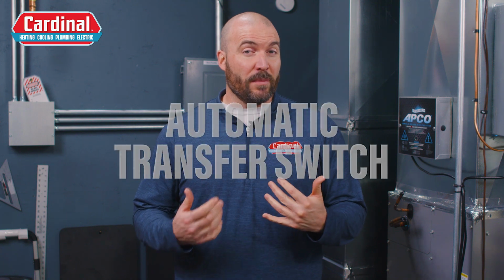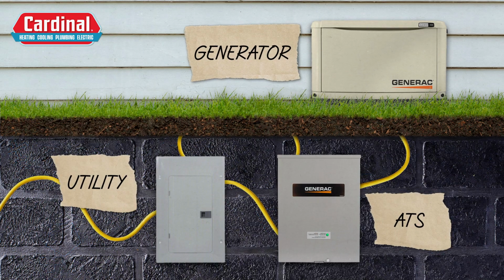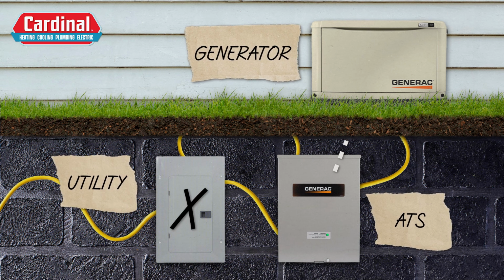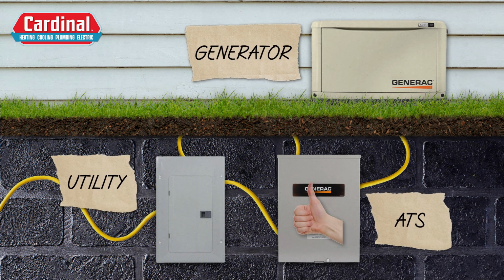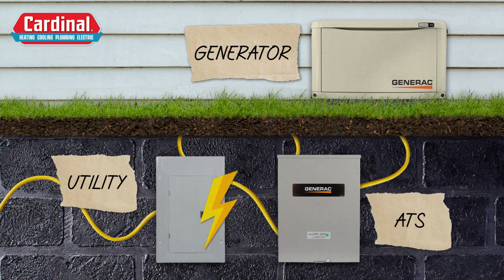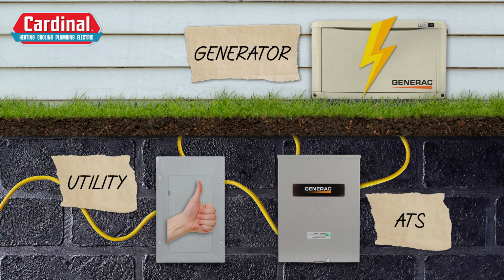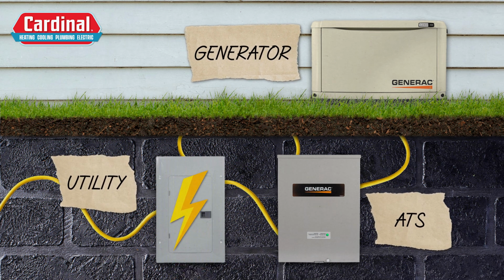A standby generator detects power outages using a device known as an automatic transfer switch. The automatic transfer switch is basically the middleman between your home's power, your utility power, and the generator itself. When a power outage occurs, the automatic transfer switch will communicate with the standby generator and tell it when to start running. Once the automatic transfer switch detects that the generator is running and stable, it'll immediately shift the electrical load from utility power to generator power. It works the same in reverse. Once the automatic transfer switch detects that the power is returned, it'll shift the load back to utility power and tell the standby generator that it can start shutting down.